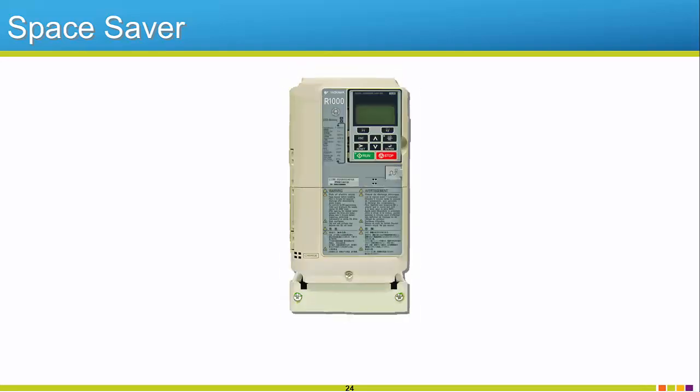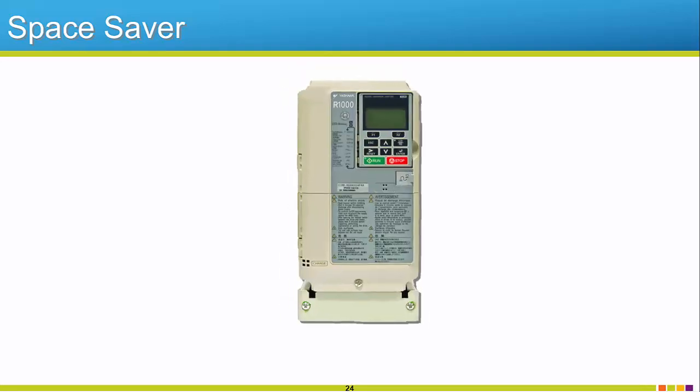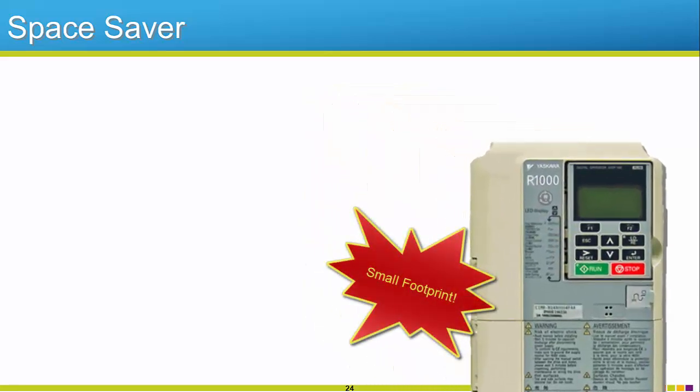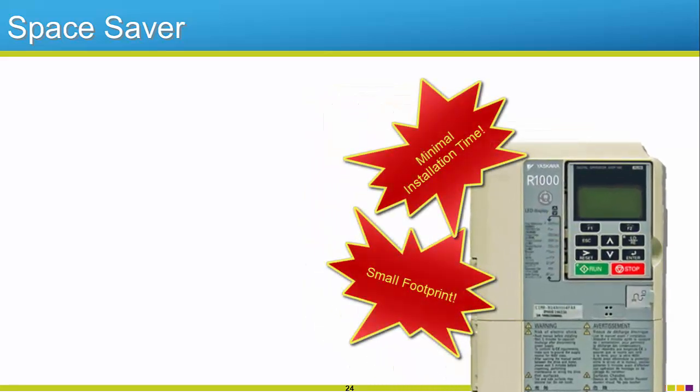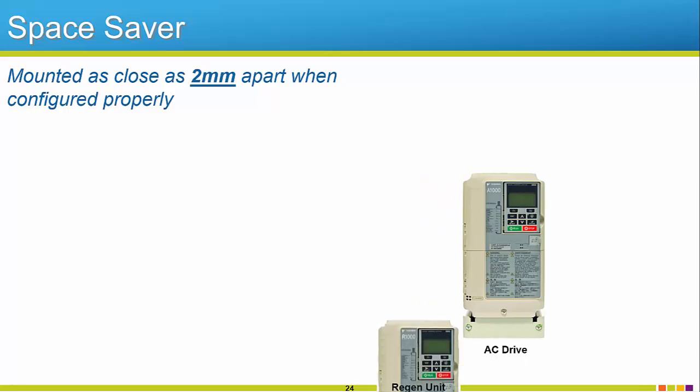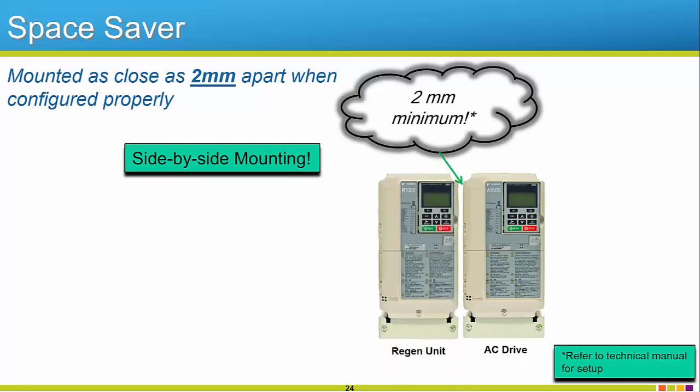Here at Yaskawa, we understand how important and costly space is. The R1000 design features various size and installation reductions resulting in less space needed and a quicker installation time. To sweeten the deal further, the R1000 can be mounted as close as 2 millimeters side-by-side next to the drives it's connected to. This is virtually touching, and will maximize the limited space you may have. Be sure to reference the technical manual for further information about a side-by-side mounting setup.